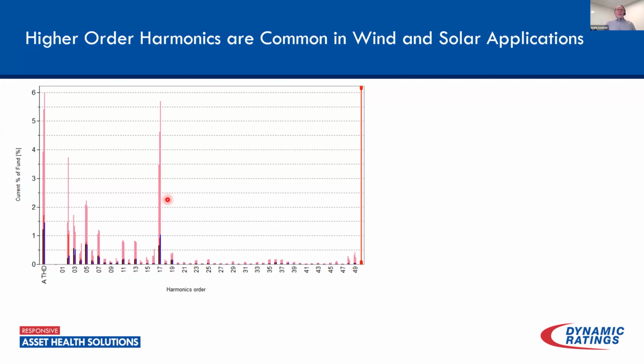Now, a little bit later, I'm going to also talk about the effect of harmonics. I think everybody's pretty aware of the effect that harmonics can have on aging and the thermal process, the temperatures within the transformer. But that's not the only problem that we're worried about. Harmonics can also impact partial discharge and things like that. And that's a piece that's very, very interesting.